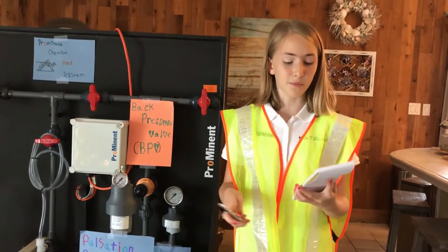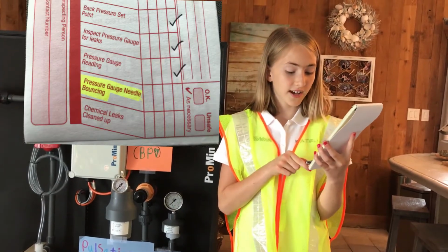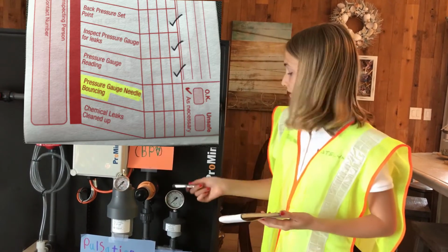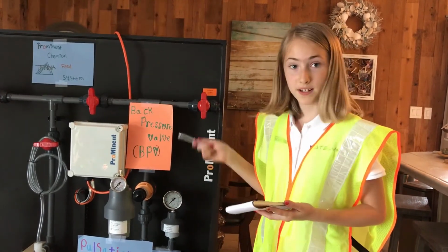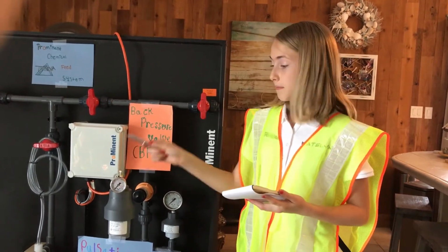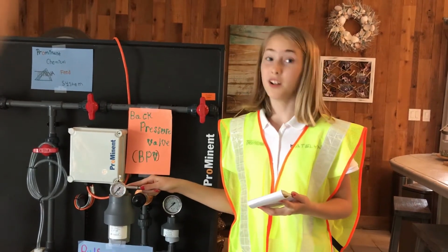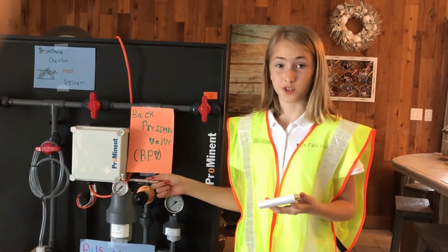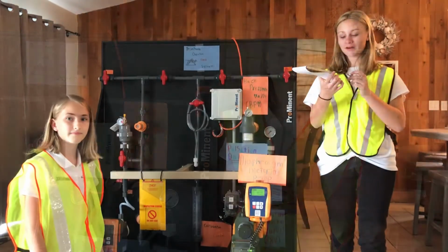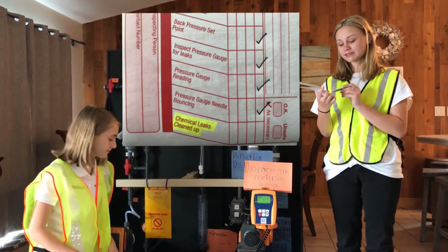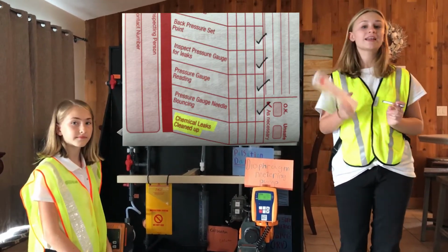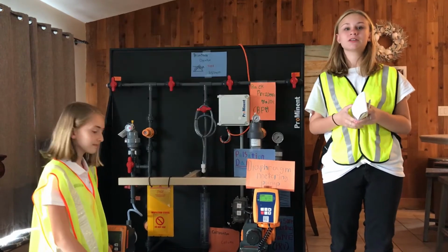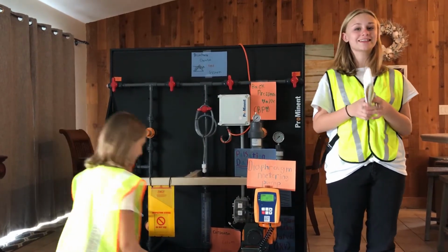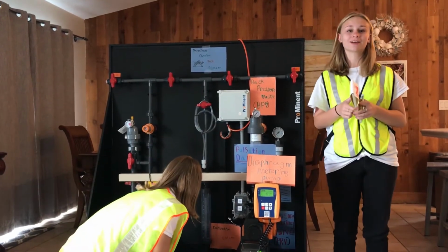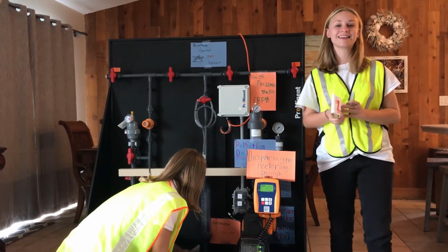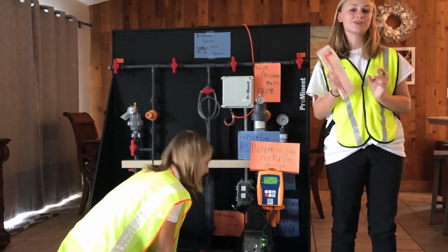Step 16 on your booklet is pressure gauge needle bouncing. If this is going up and down like it's bouncing, that means that the pulsation dampener is not working or you need to install one. The final step is chemical leaks cleaned up. If you had any prior leaks, be sure the skid floor is cleaned. This will allow you to quickly assess if there are any new leaks in your system.